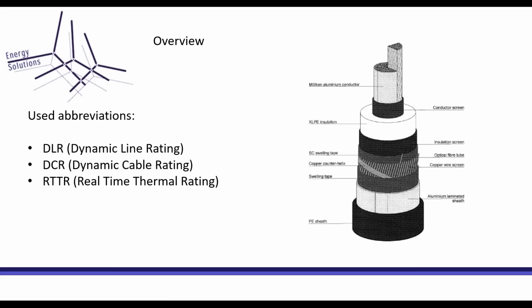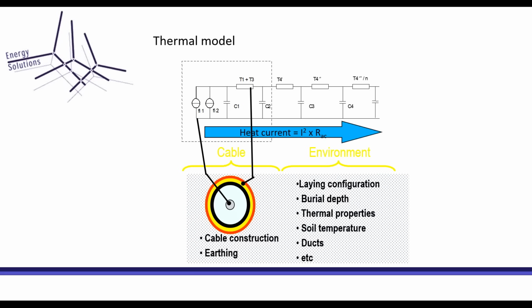What we normally do is make a thermal model of the cable itself. So you have a heat source, mainly the conductor losses. You have a thermal capacitance, and you have a thermal resistance of the insulation. And then you also have the environment part, which is also quite important, because when you have a new cable route installed, it goes through many different laying configurations, and all these laying configurations must be modeled in thermal models to make sure you calculate the right thermal rating of the cable.